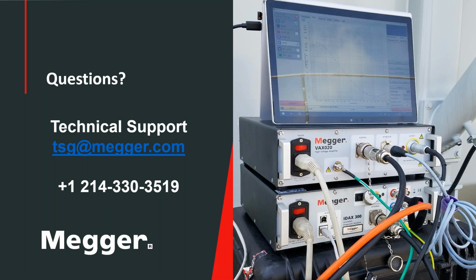That's the typical Idax. But if you look into some of the CIGRE reliability reports that we have in the technical brochures, you have seen the influence of bushing failure on the overall failure of a power transformer. That's the reason why now more than ever, dielectric diagnostics on high voltage bushings is quite important.